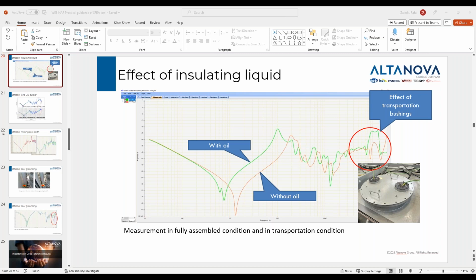And if such influence is valid there and you cannot switch off the line, and your leads are still picking up and inducing some currents, the best thing you can do is to understand that at 50 Hertz and around there will usually be some noise visible. They are affected by this phenomenon. This has nothing to do with winding deformation. If there was a winding deformation, it would progress further through frequencies. So that would be the case.